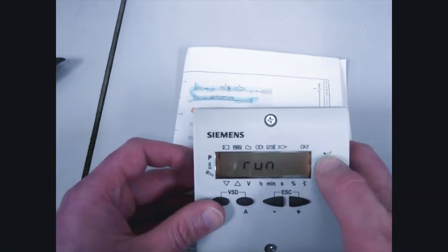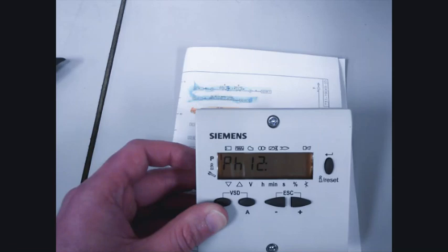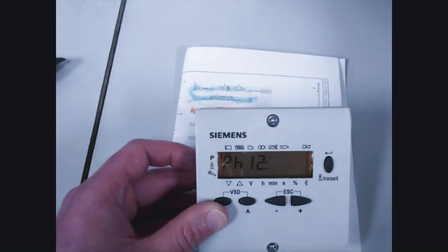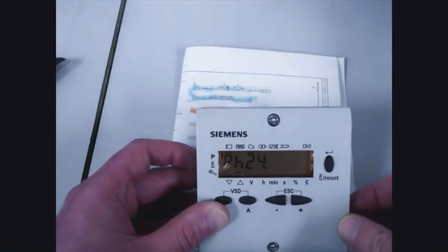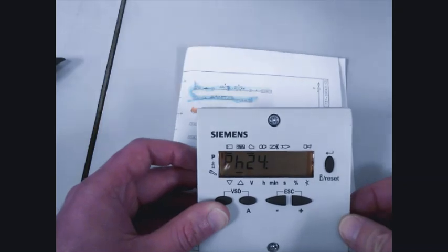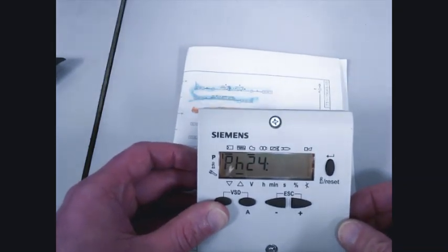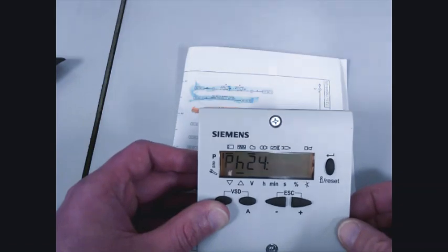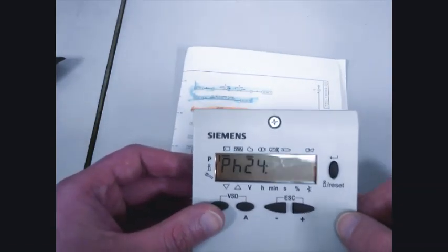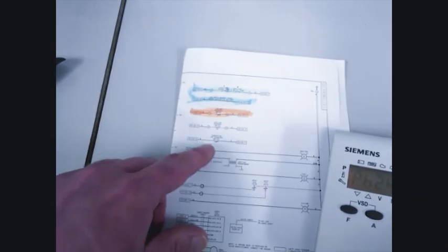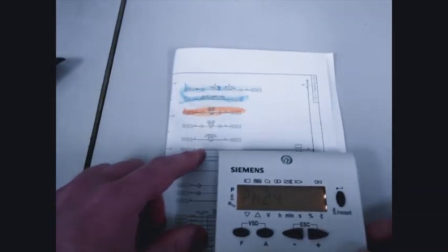Enter, enter. Turn the burner switch on. Now with our low gas pressure made, the blower motor is still on, as previously in phase 12 while waiting for low gas pressure. It will stay here until combustion air is made at X302.1.